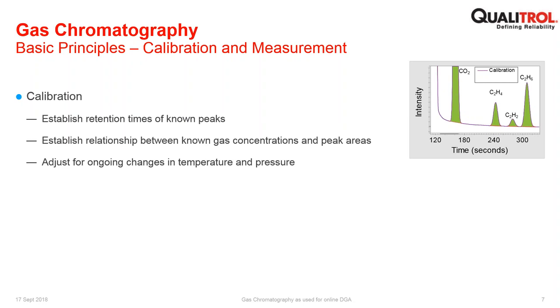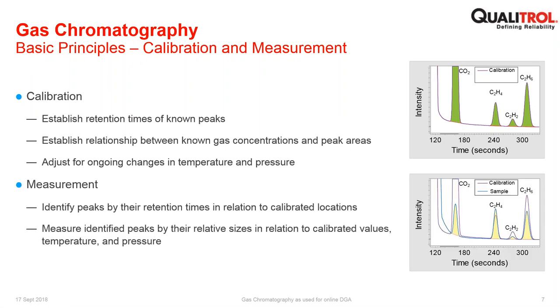So the size of the peak is directly related to the concentration. So that's where the quantitative element of the measurement comes in. So the time is the qualitative, and the size of the peak is the quantitative. And of course, it can be adjusted for changes in temperature and pressure. And then for measurement, so that's calibration.